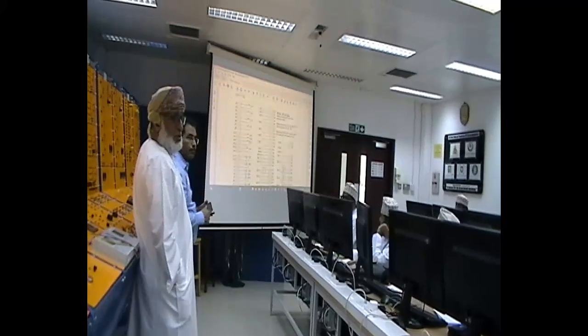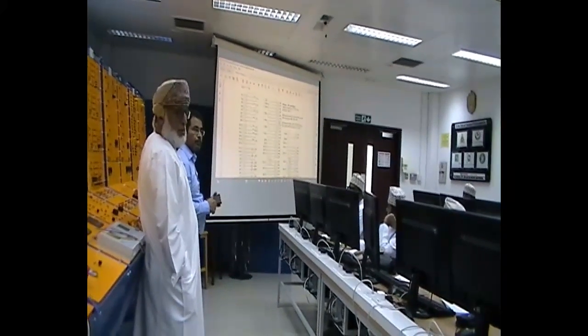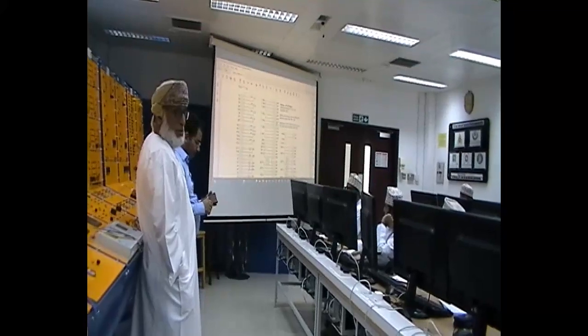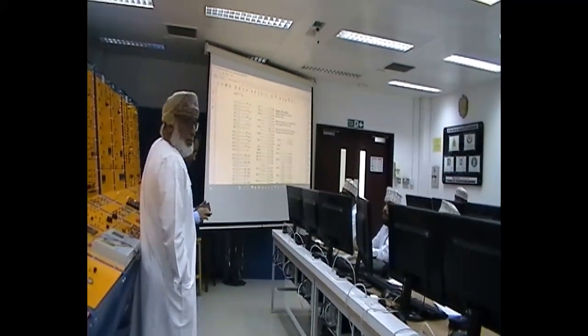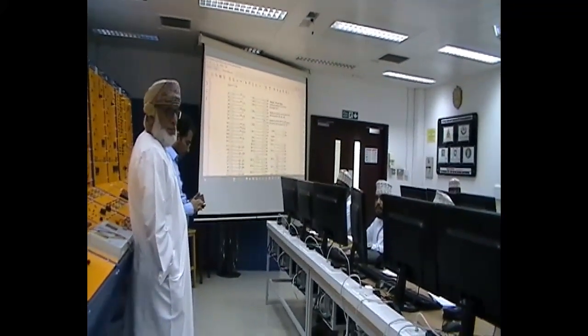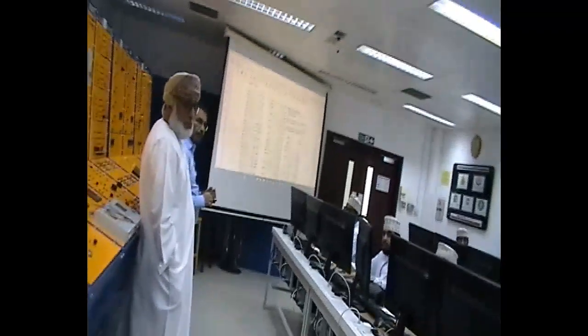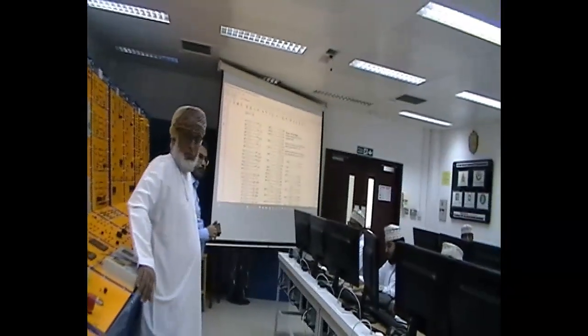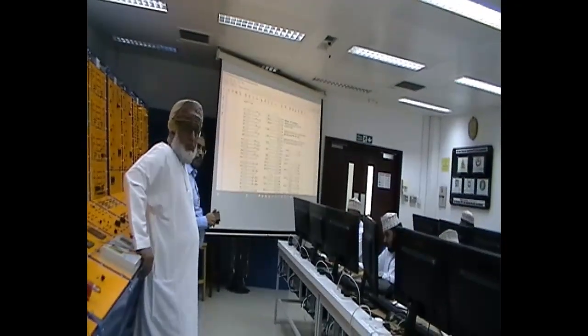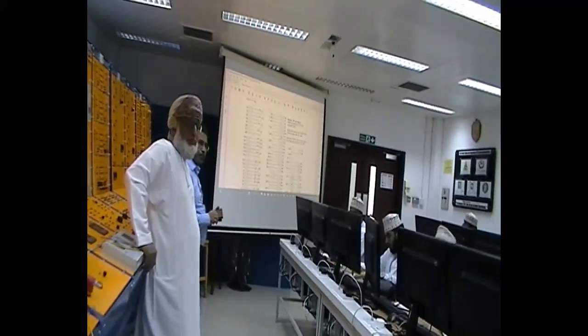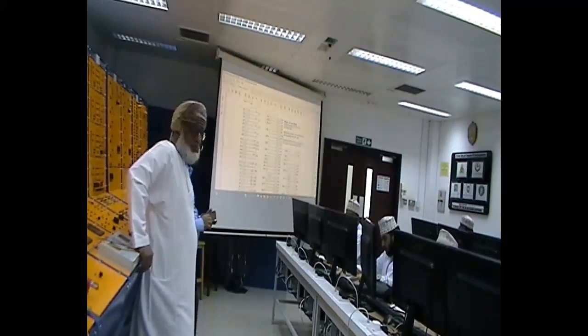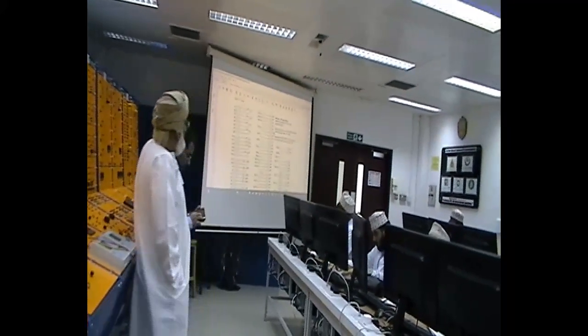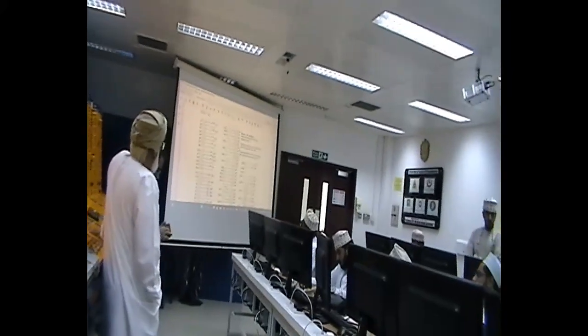Now that is the trip signal, and we route one other signal, just the pickup before the trip. Once it starts counting, like an alarming signal, to see the sensitivity of the setting. For example, in overcurrent the setting is in current, so it's 400 ampere. I wanted to see whether it starts counting once it reaches 400 ampere or not. Maybe it's delayed. So that we call the pickup, and usually we'll take it just for the feedback in the test kit, so to check the sensitivity of the setting.